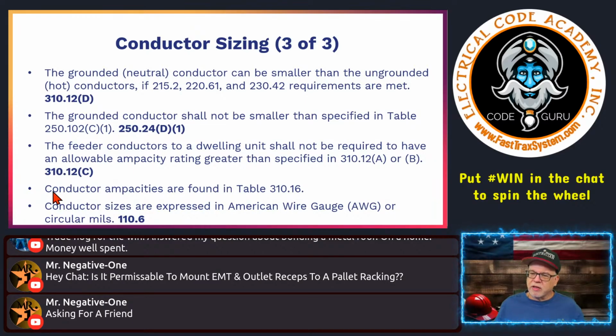All right, so the next one, conductors' ampacities are found in table 310.16. Conductor sizes are expressed in American wire gauge, as y'all know, or circular mils. So once you get up to 4/0, you'll go to chapter 9, table 8 to see your circular mils, right? And when you get over that, it's expressed in circular mils. 250 kcmil is 250,000, 300 kcmil is 300,000, k being 1,000, cmil being circular mil, that type of thing.